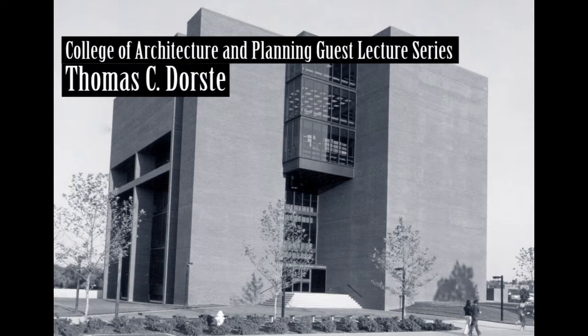And the only way we could put the study together was to take a typical year's program, align the use of the building with the information we got from the Weather Bureau and Flight Service as to the weather for that day, hour by hour. And we ran it 12 times through a computer program. And believe it or not, with about 18,000 square feet of collectors on the roof and 45,000 gallons of storage, we could pick up 43% of the heat requirement for the building. And you've got to recognize that when there are 12,000 people in the building and the lights are on, there wasn't any requirement for heat at all. It was a requirement for air conditioning.